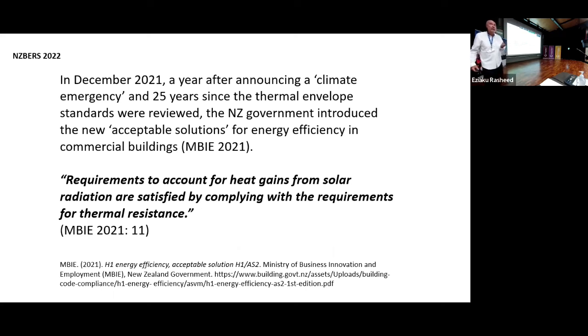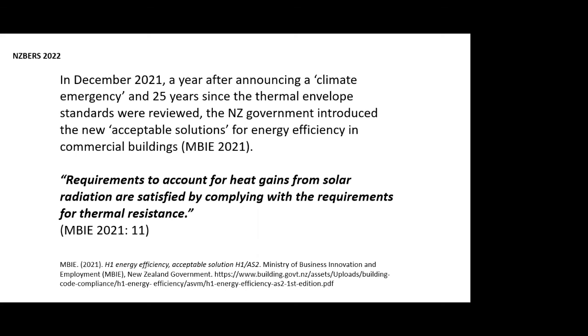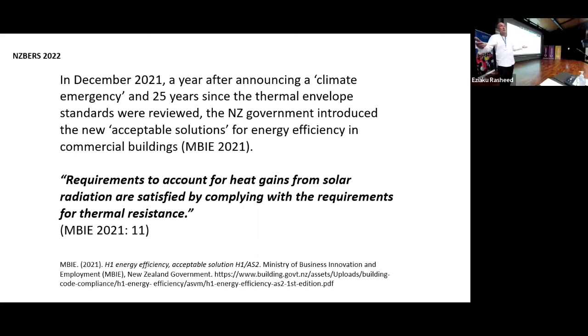If you put in double glazing instead of single glazing, which is probably going to be the result - but we'll have to see of this regulation - yes, you will reduce the cooling load and the heat. But the most important thing, if you are looking at reducing heating load, you may want to look at using passive solar energy - orientating your building so that in the winter months you make use of the beneficial heat gains from the sun.